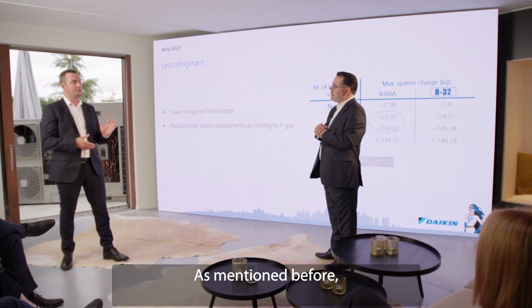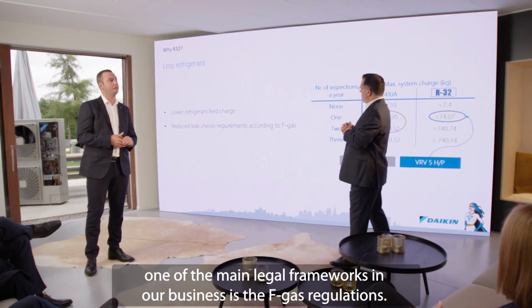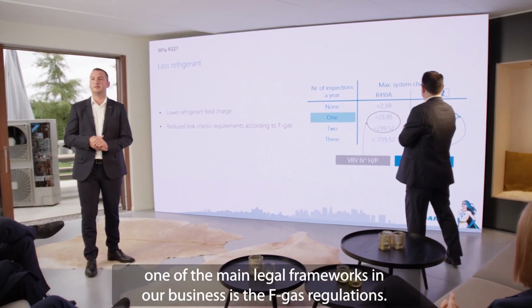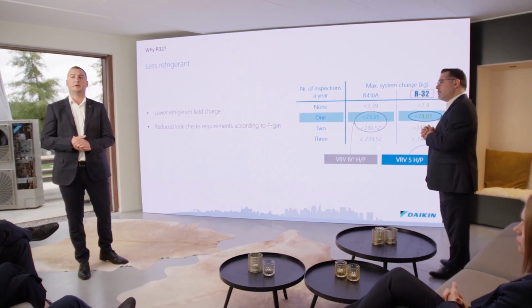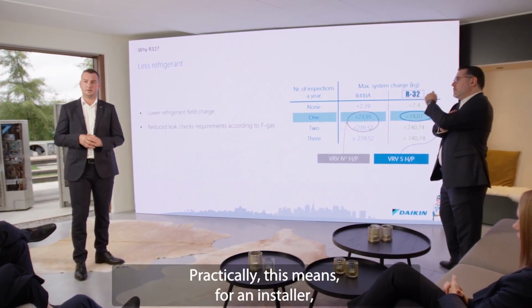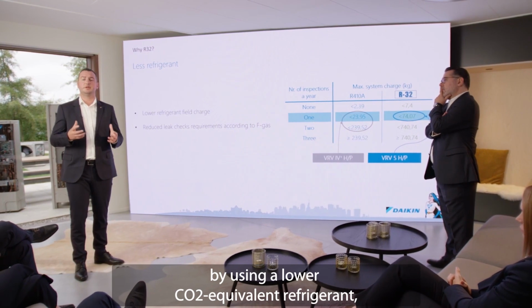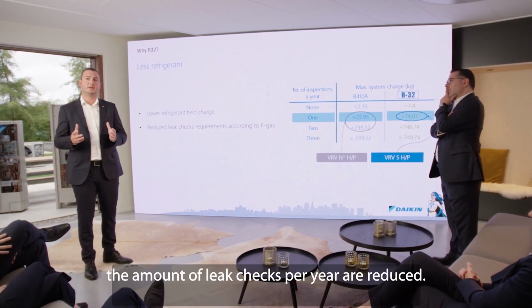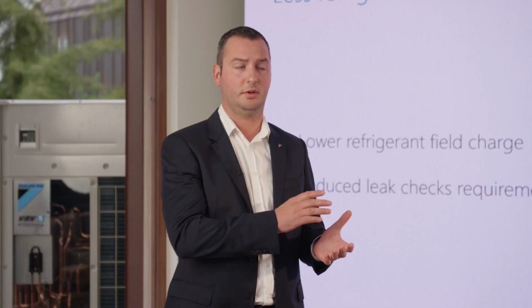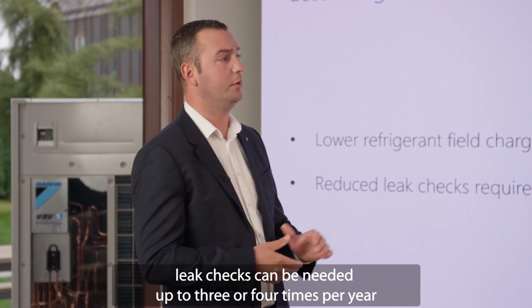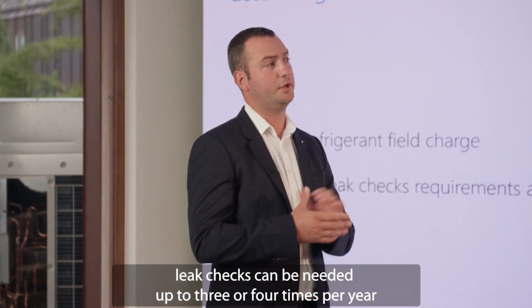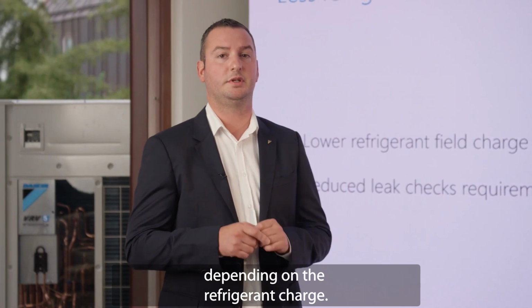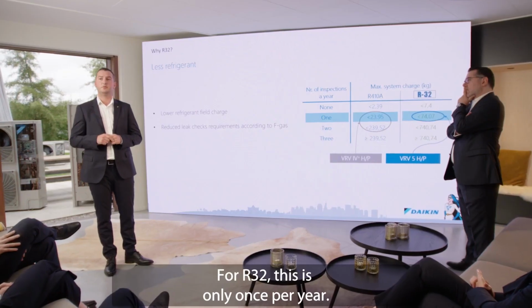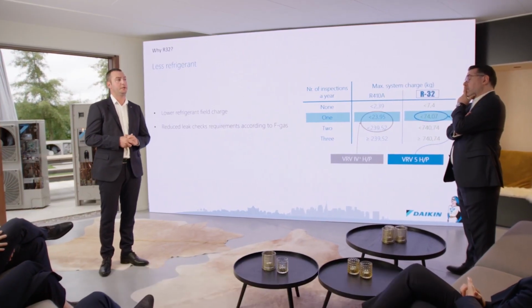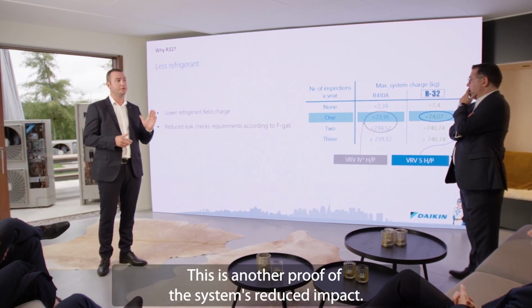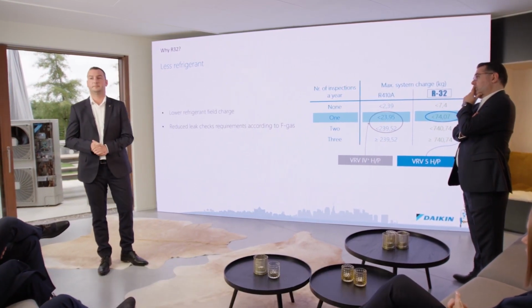As mentioned before, one of the main driving legal frameworks within our business is the F-gas regulation. Practically, this means for an installer, by using a lower CO2 equivalent refrigerant, the amount of leak checks per year are reduced. Compared to R410A, the amount of leak checks can go up to 3 to 4 times per year, depending upon the refrigerant charge. For R32, this is only 1 time per year. This is another proof of the system's reduced impact.